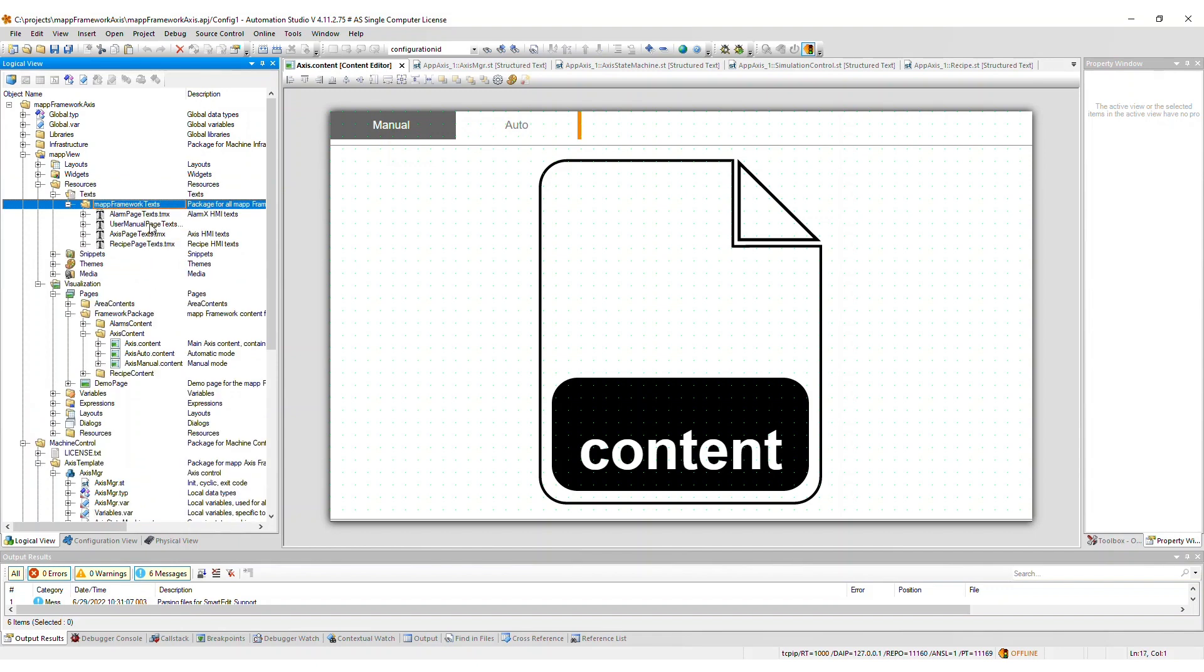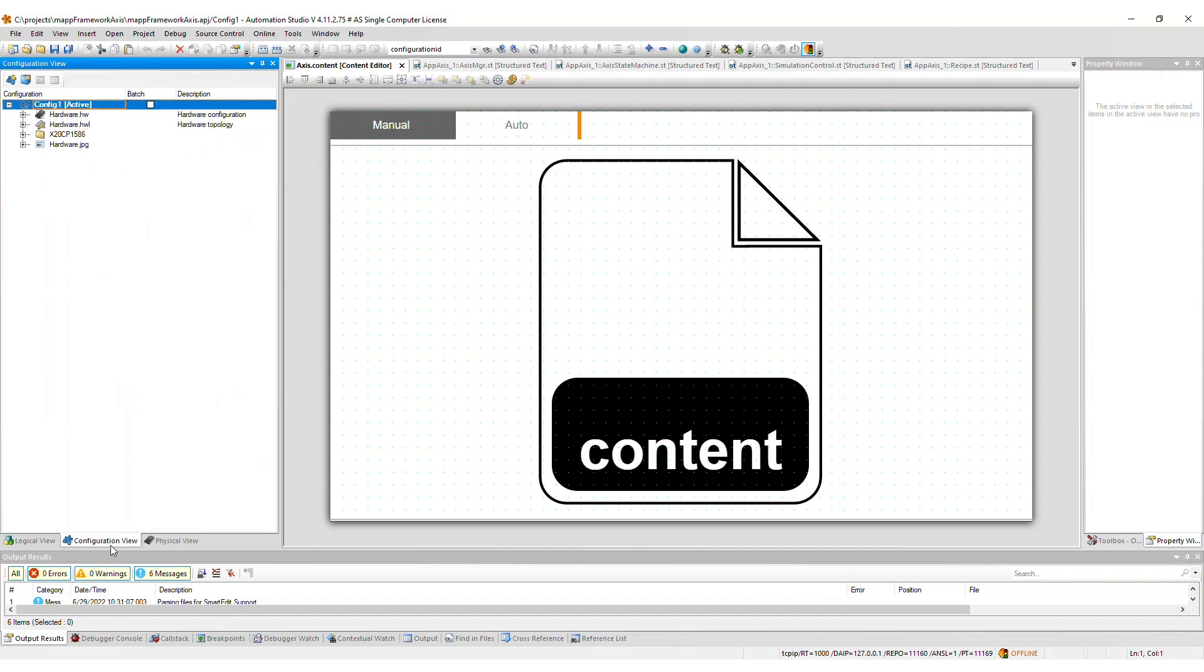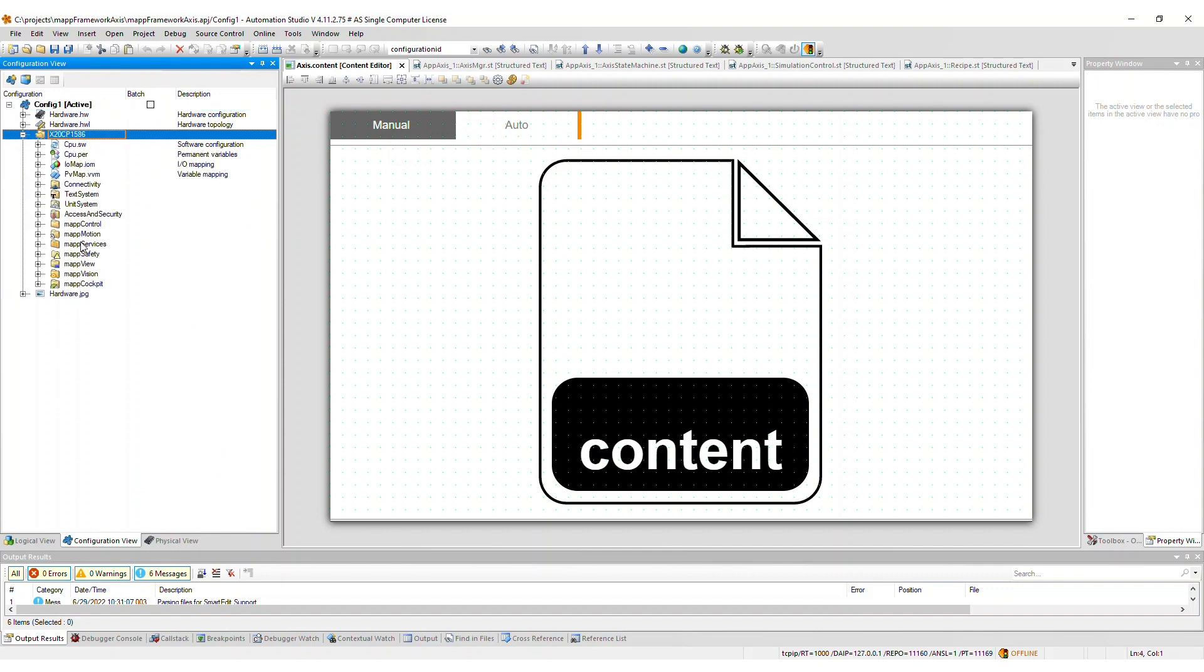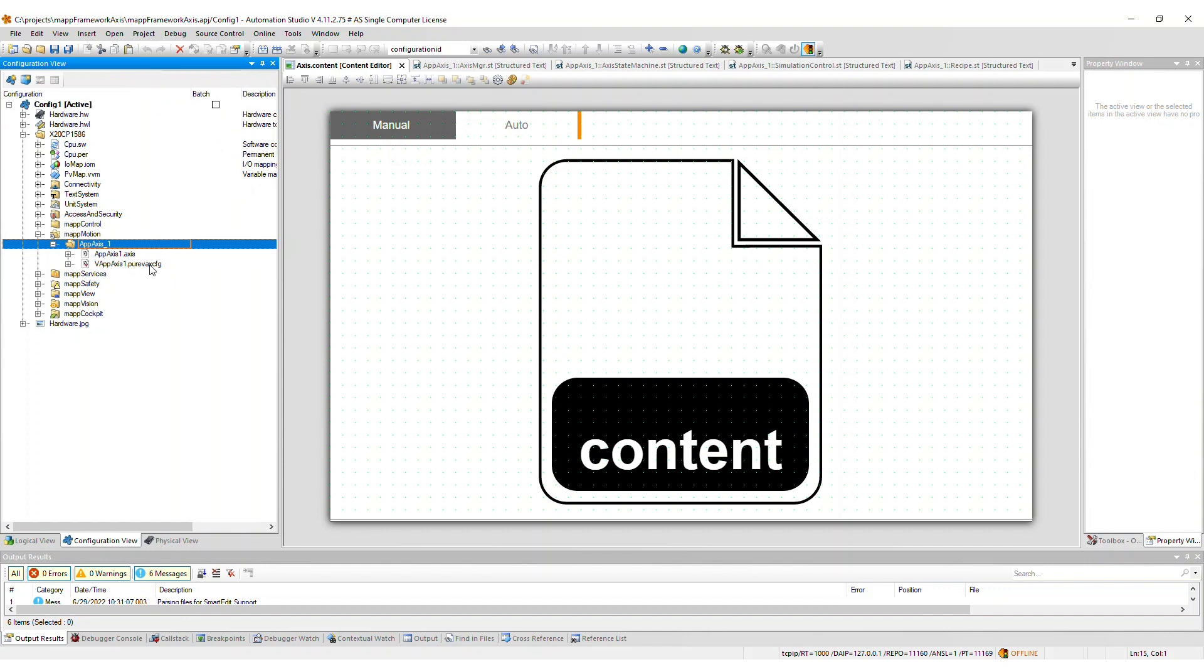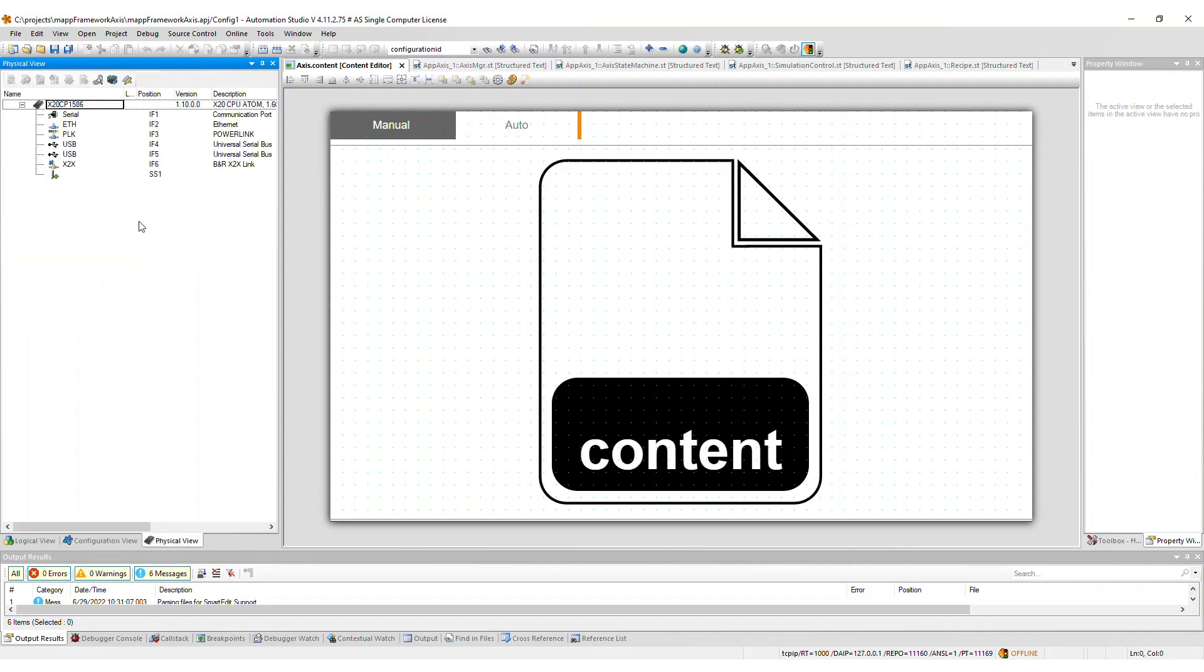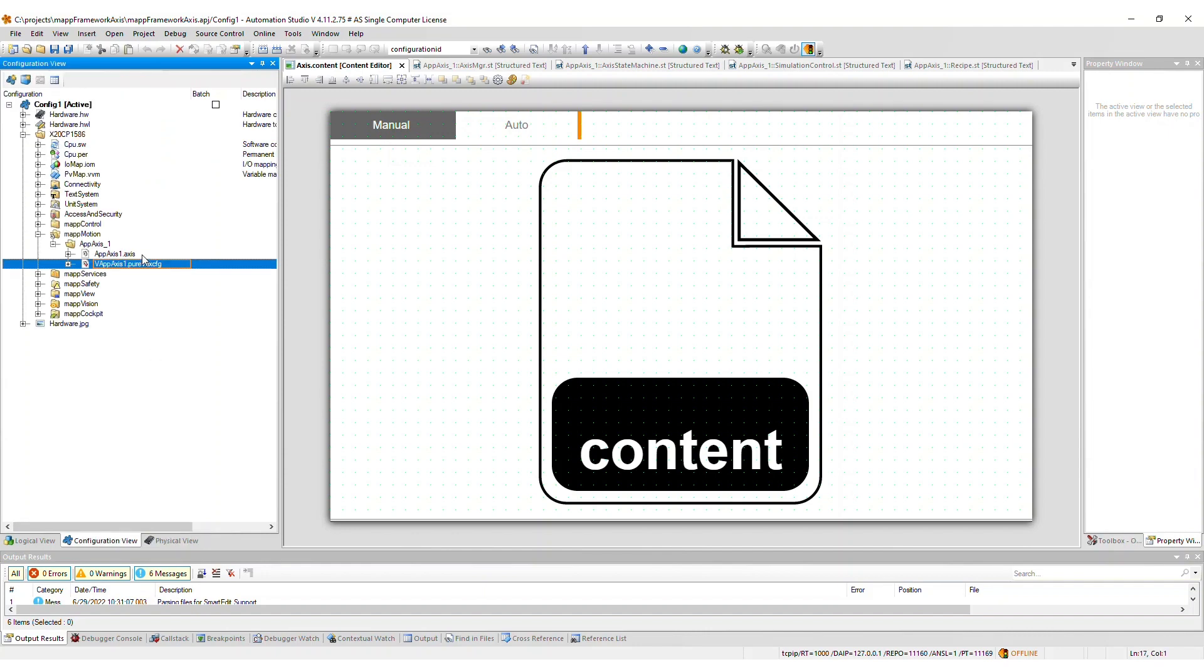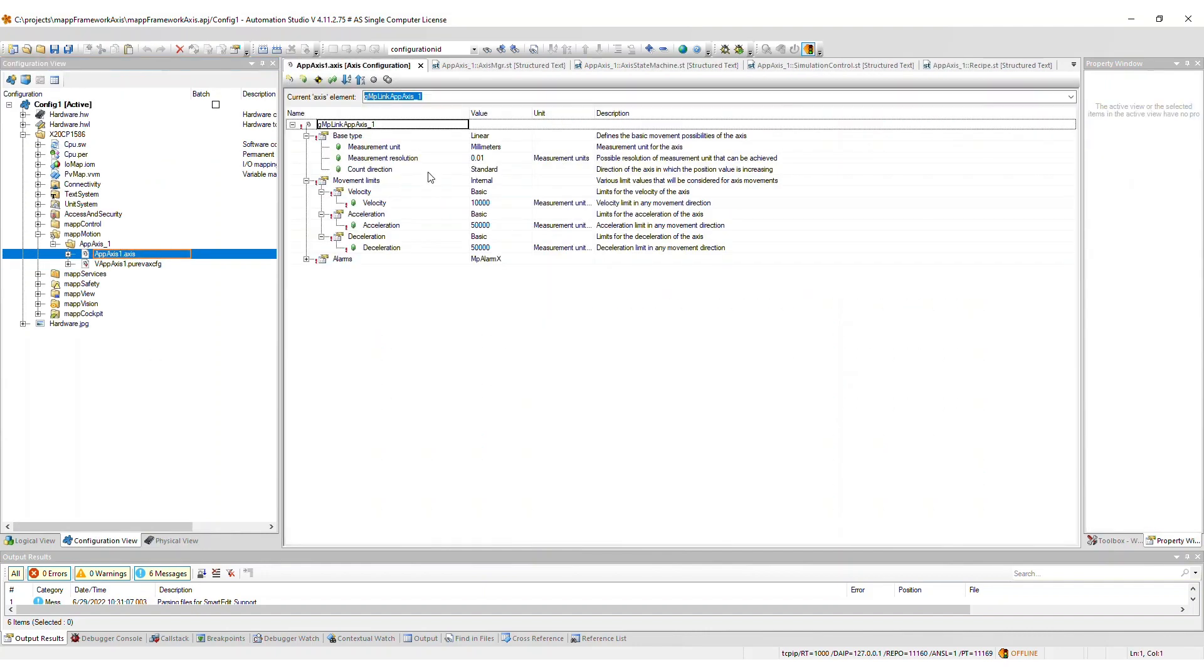Moving on to the configuration view, an AppAxis1 package gets added to the mappMotion package. Here you see the Axis configuration file and the virtual Axis configuration file because by default, the first application Axis is configured to be virtual. If you plan to run the Axis on physical hardware and not in simulation, then add a drive to the physical view. In the drive configuration, set the Axis reference to the mapp link from the single-axis configuration file. Then delete the virtual Axis configuration file.